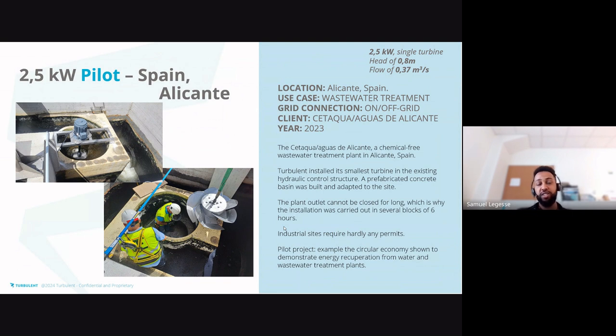It's also an on-grid or off-grid setting, meaning it works whether the turbine is connected to the grid or not. So it has a flexible option, which is also what makes it a bit more expensive to mention, because it can work in both on and off-grid settings. Whenever the grid is down or disconnected for some reason, the turbine can still generate energy. In normal on-grid turbines, the system is synchronized with the grid, so whenever the grid is down, the turbine stops generating. But in an off-grid case, there is no grid — our turbine becomes a grid-forming turbine. Or in a hybrid off-grid scenario with solar, either the solar or the turbine will create the grid, and the other will follow that grid frequency. So unless the turbine itself stops working, there won't be any disruption of energy in an off-grid context.